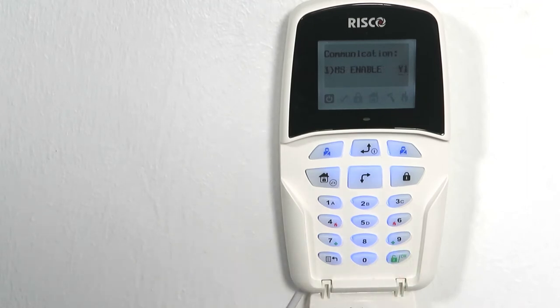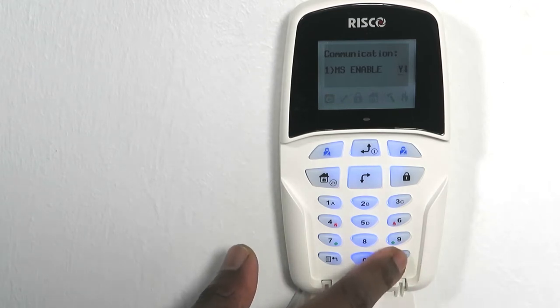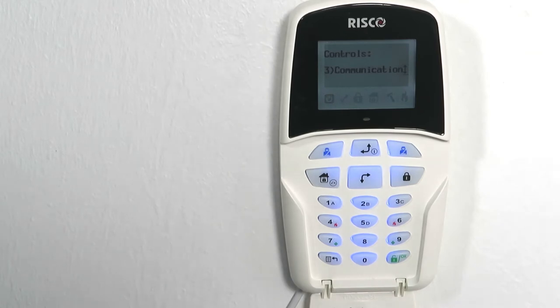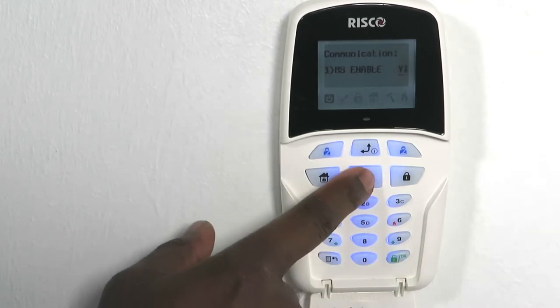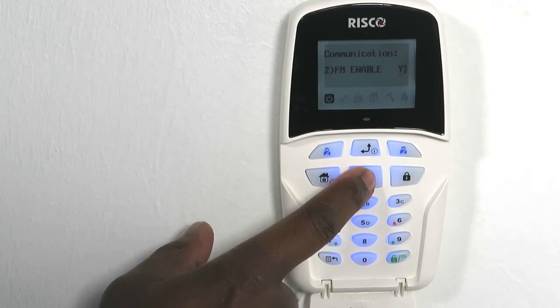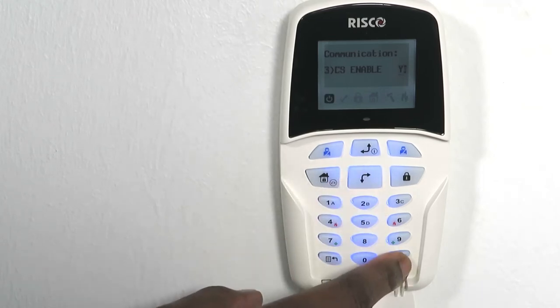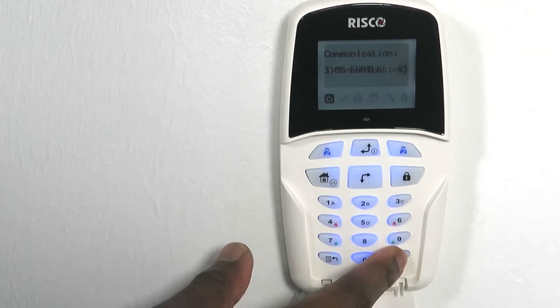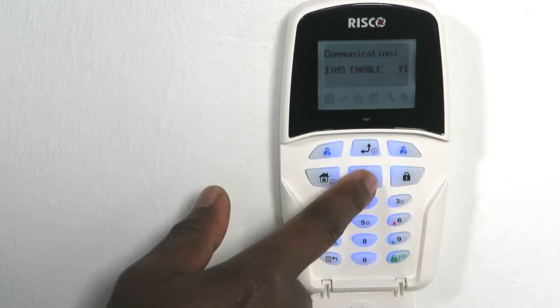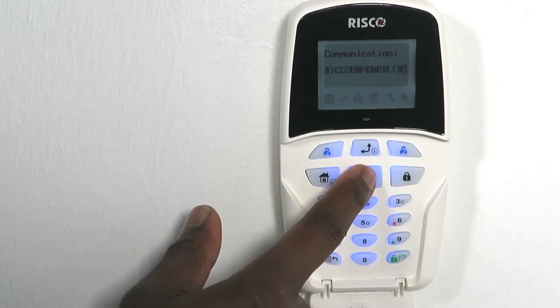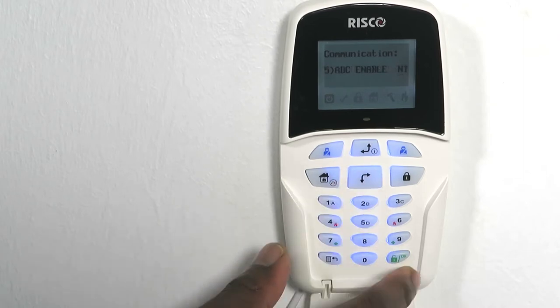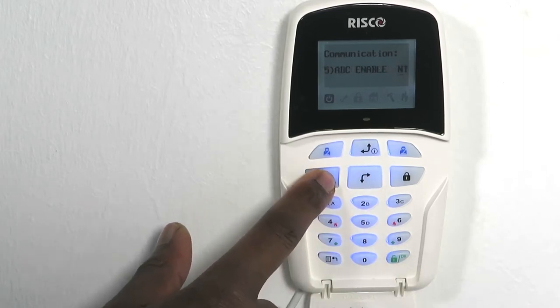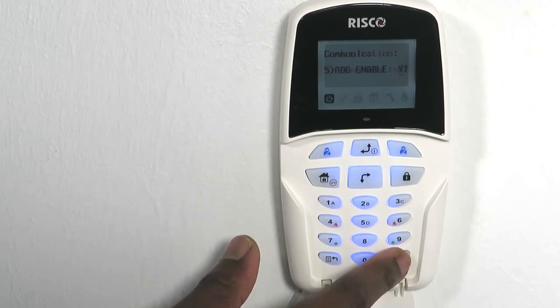Set MS enable or ARC enable, depending on whether your panel is set to the UK or international language option, to yes. Press OK to enter the communication menu again. Scroll down to CS enable and set to yes. Re-enter the communication menu by pressing OK. Scroll down to ADC Enable and set to Yes. Press OK and press the menu button 2 times.